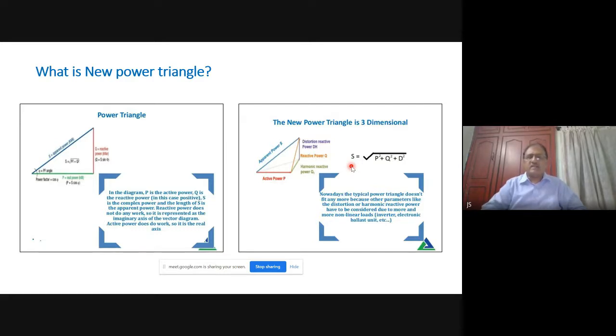Wherever in the states people have gone for kVAH billing, if the distortion power is also considered in the trivector meter, and instead of penalties you are getting a kVAH increase compared to kWH, then you have a choice of addressing the distortion power factor as the cause of this increment in kVAH. So again, I suggest you use a good quality power analyzer at the point of common coupling. Use it for 24 hours. Download the data and analyze, including kilowatt, kVAR, and the distortion power, D square. So this is very important.